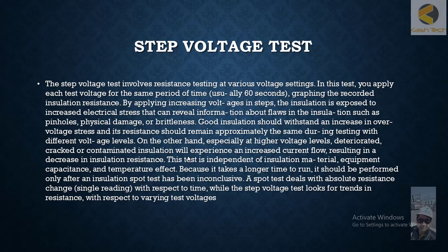In the step voltage test, you apply different sets of voltages for a fixed time and check the response of the insulation. Good insulation would have very small change in leakage current and the insulation level will be fairly constant. But if the insulation is not good, you will see a drop in the graph.